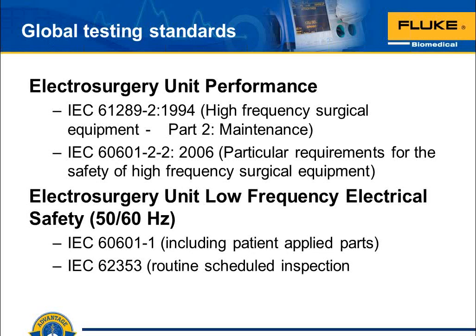There are global testing standards relative to the ESU and the ESU generator's performance. And we're going to look at primarily the IEC standards, but I want you to know that the ANSI standards also have been harmonized to these IEC standards. So we're going to call out the IEC standards here. The IEC 61289-2, 1994, high-frequency surgical equipment, Part 2, has to do with the maintenance of high-frequency surgical equipment.